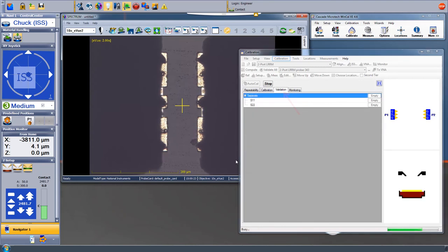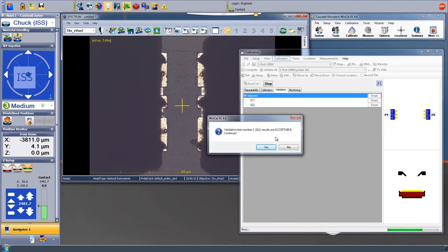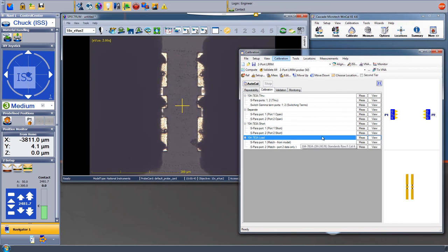Once this is done, we confirm the file name for the calibration file to be saved on the network analyzer. Moving over to the Validation tab, the software then double checks that S11 and S22 are both reasonable when it's measuring a load. Looks like they are good. And that's it. You just witnessed an automated on-wafer network analyzer calibration to 50 GHz.